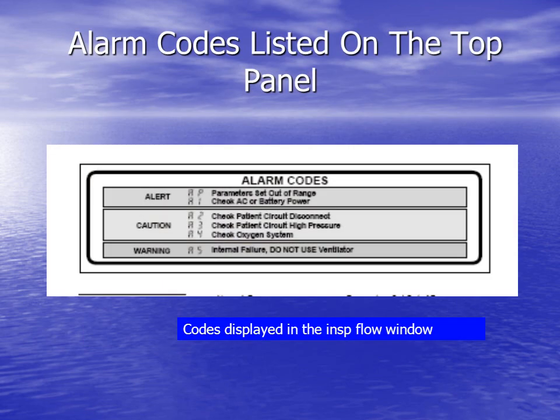It would be impractical to ask clinicians to memorize all the possible alarm codes. For this reason, a chart is placed on the top panel of the PLV indicating the meaning of the codes. These codes will be displayed in the inspiratory flow window readout. An A1 alarm might display when you plug or unplug the unit, as it has had to switch to its internal battery. A2 is a disconnect alarm.